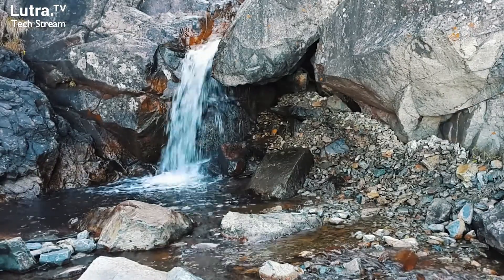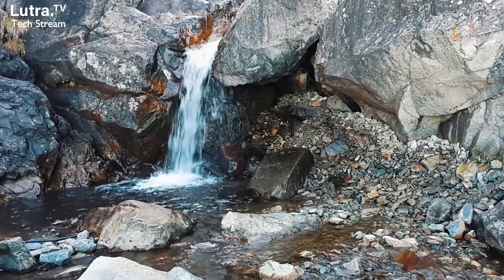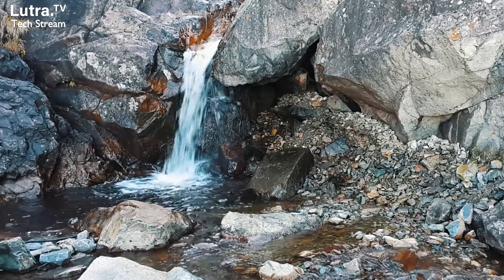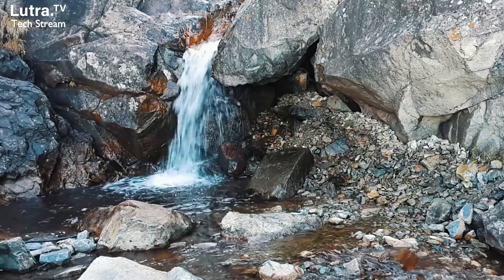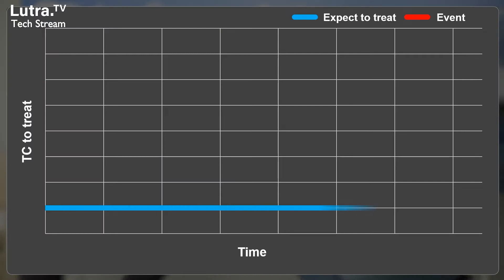Whether we look at source water or treated water, let's look at source water first. By monitoring source water, you're deciding what's going on there - it's about knowing your source water and knowing the baseline. The trouble with E. coli is the baseline is zero, so it can't go down from zero and you can't see water quality getting better. But if you've got a baseline that's not zero, you can see quality improving or deteriorating.